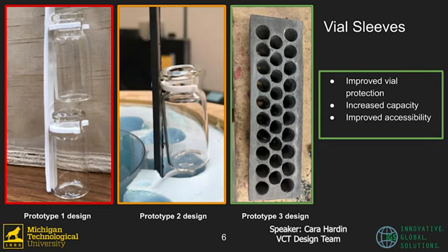Our vial sleeves have three main advantages, the first being improved vial protection. In the previous prototypes, the vaccine vials were directly exposed to the insulation. With our new design, the vials are surrounded by foam sleeves to ensure the vials are thermally and physically protected.